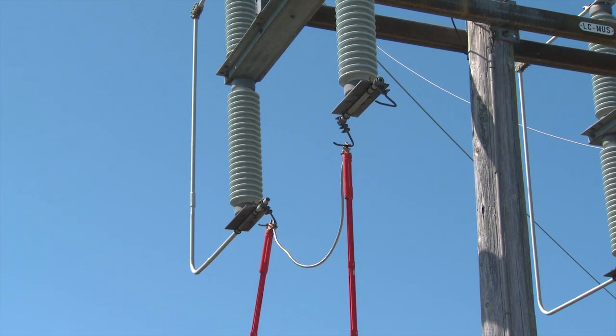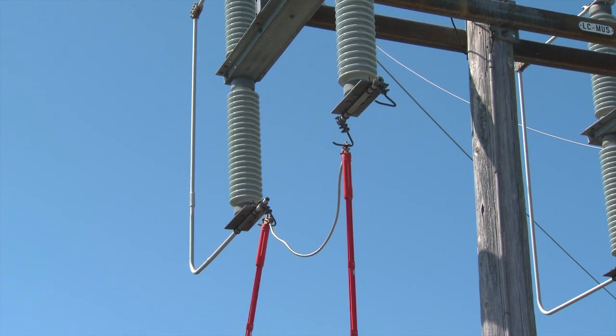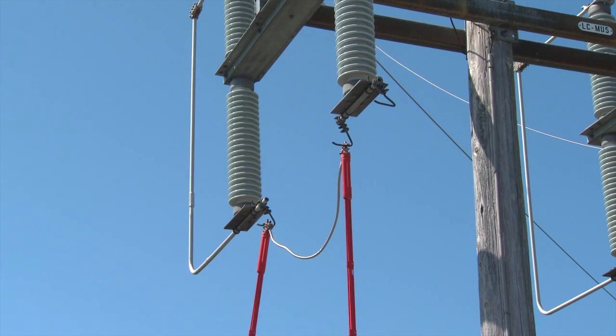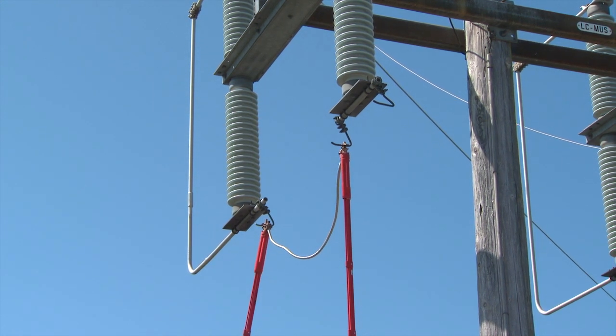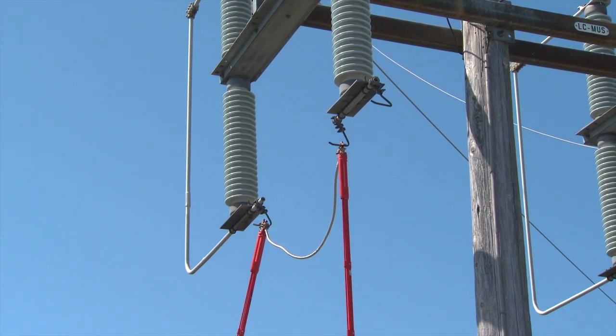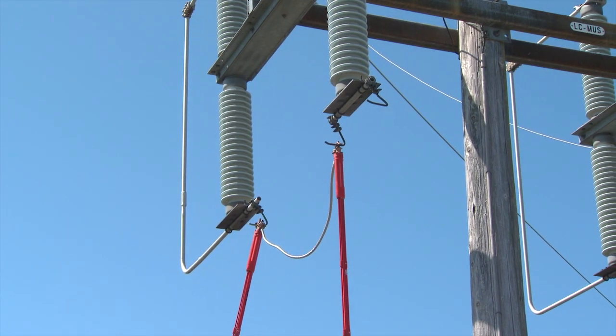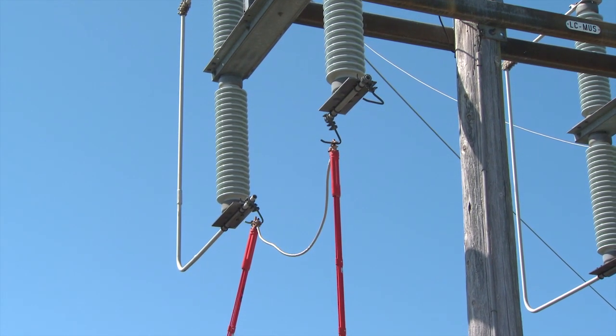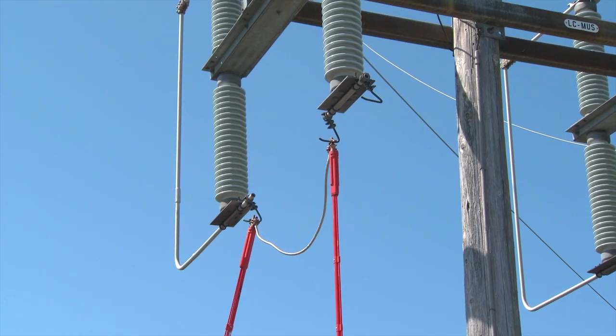If a station doesn't have a 115 kV MUS connection structure, the high-voltage leads will need to be installed on the 115 kV tower line conductors. A provincial lines crew should be contacted to install stirrups and assist with high-voltage connections.